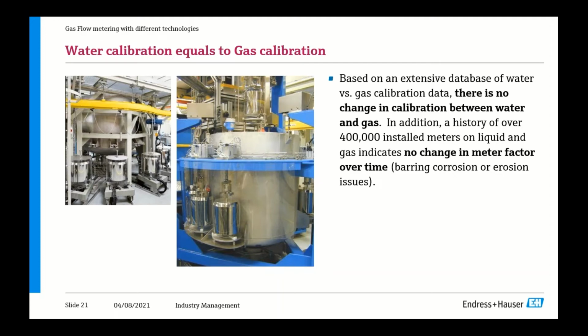So first, what we do is establish the meter factor on water. That's pretty much standard for Coriolis meters. Then, as a second point, we validate the meter factor on gas. That can be done at a third-party facility, for example, PIGSAR here in Germany. And the third point will be to periodically remove the meter from service and verify the meter factor on water.